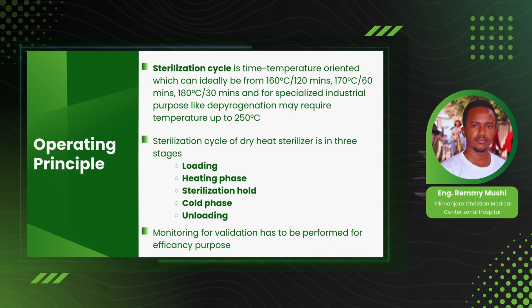And the third stage, or the fourth here in our case, is the cold phase or cooling phase. The cooling phase is a stage where the temperature drops from the one that you set to a lower temperature. It can be around room temperature, or around 80 degrees, depending on how fast you want to take out your load. But it is mostly recommended to ensure that the temperature inside is lower, so that it does not burn you as you take out the load, because at a temperature of 180 degrees or 120 degrees, the kind of energy it possesses, if you put your hand inside, it can give you even a third-degree burn. So it is really important to ensure that the cold phase drops the temperature to a safe level, which is around 20 up to 40 or 50 degrees, or even 60 in some cases.